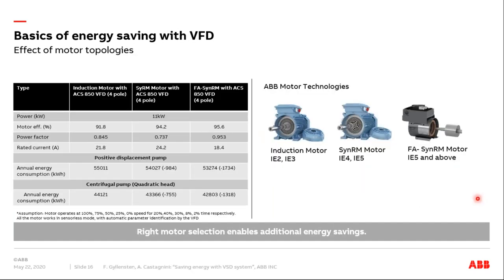I want to go to another example, where I include different motor topologies. In the first slide we talked about going from fixed speed to variable speed. Now I want to talk about having variable speed on all the systems, using the different motor topologies that we talked about before. You have the induction machine. You have the synchronous reluctance machines that we talked about. We can go to IE4, IE5. ABB already produces both IE4 and IE5 categories. And then we also have the ferrite permanent magnet assisted synchronous reluctance machines, which go above IE5. We also produce these motors. If we compare all three motor categories together, all of these are running with the ACS 850 VFD from ABB.